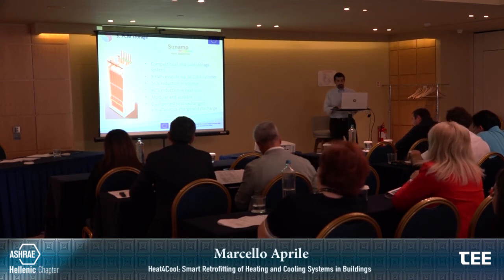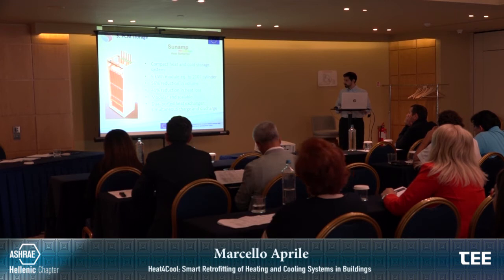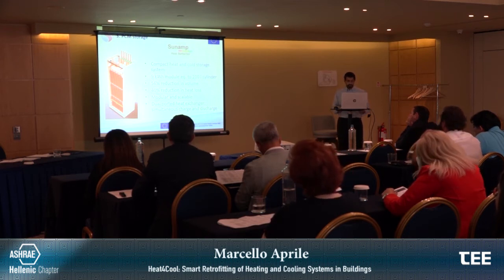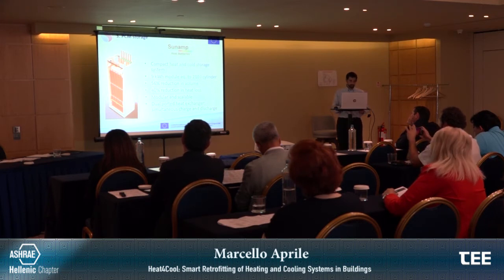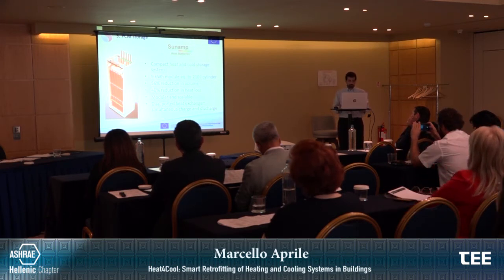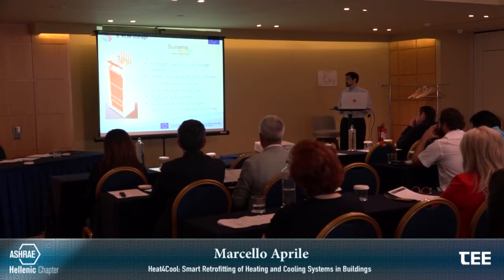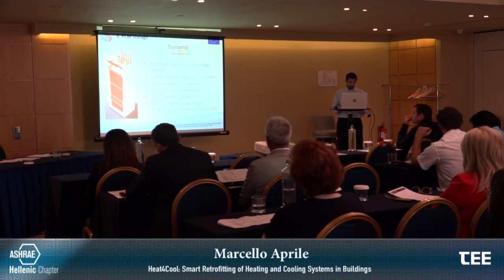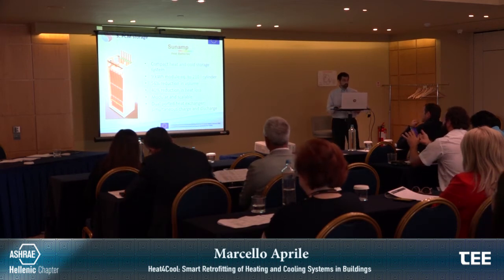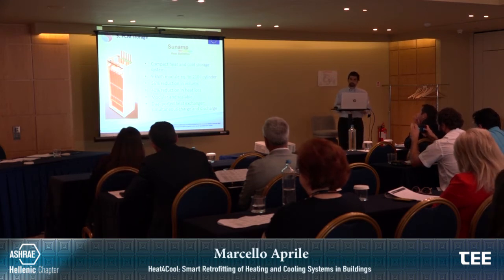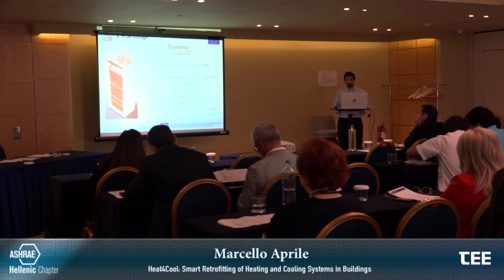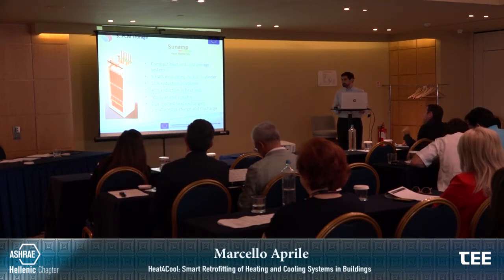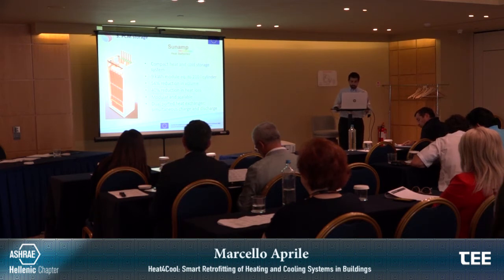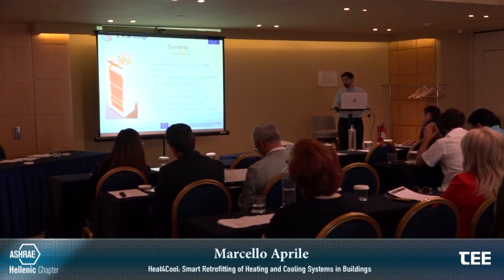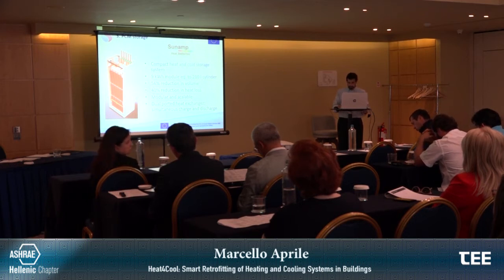In a similar way, Sunamp, another partner of our consortium, has developed a new compact heat storage, PCM based, which compared to water can guarantee 56% reduction in volume and 40% reduction in heat losses. Most importantly, it is modular and scalable, which eases installation especially in existing buildings where space for storage is normally not considered. It's a dual-ported heat exchanger, meaning you can simultaneously charge and discharge the storage—this was a requirement of our design, required by our evaluation.